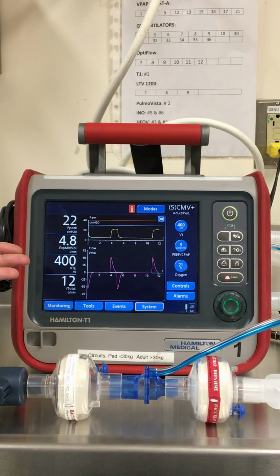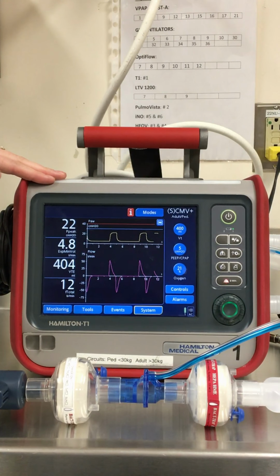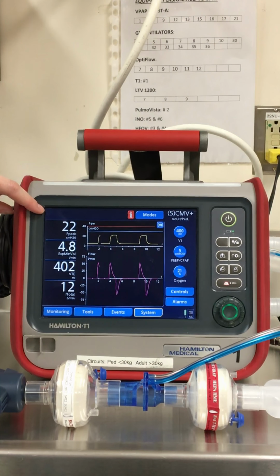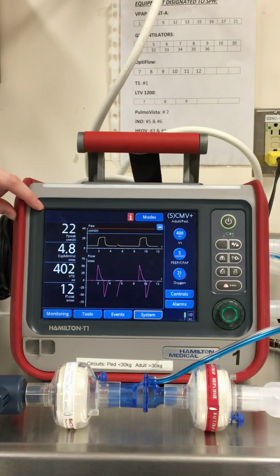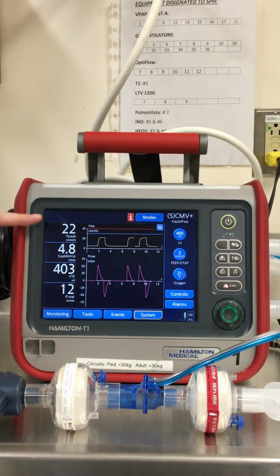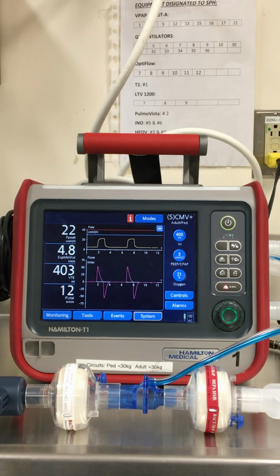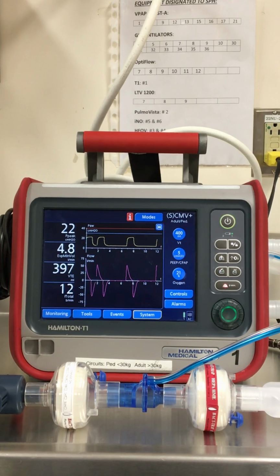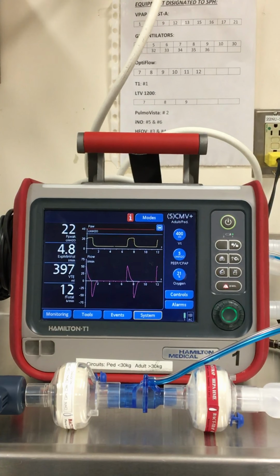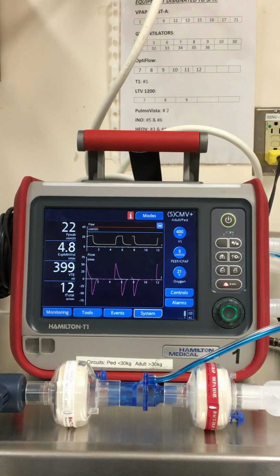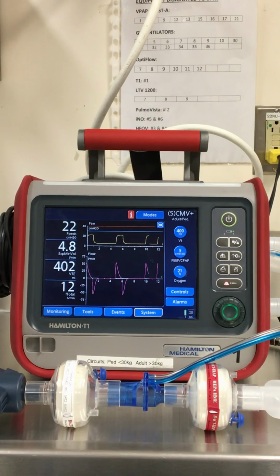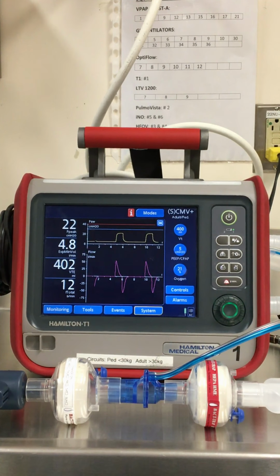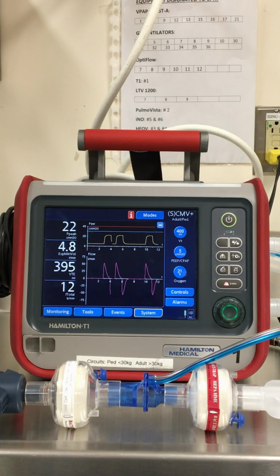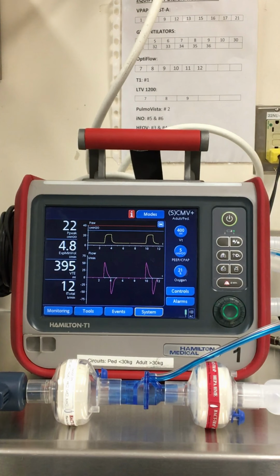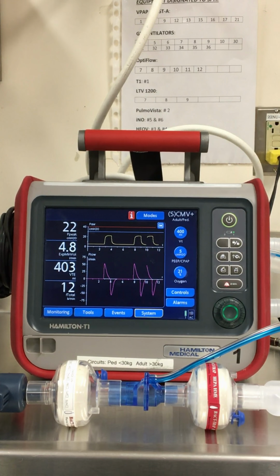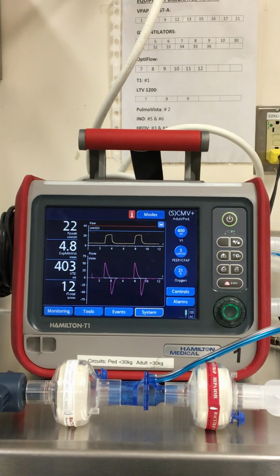Rather than for a high priority alarm, the bar will flash red at the top. The bar that you will see on the display will be red with writing inside, again indicating the type of alarm that it is, and the value that is an issue will also be written in red rather than white. I will now demonstrate an example of a low priority alarm. A common one that we'll see is tidal volume low or potentially minute volume low. This occurs if you potentially have a cuff leak around your endotracheal or tracheostomy tube, if your patient is waking or the sedation is inconsistent and they are therefore taking some small breaths and some large breaths. Just 2 examples of when this might happen.